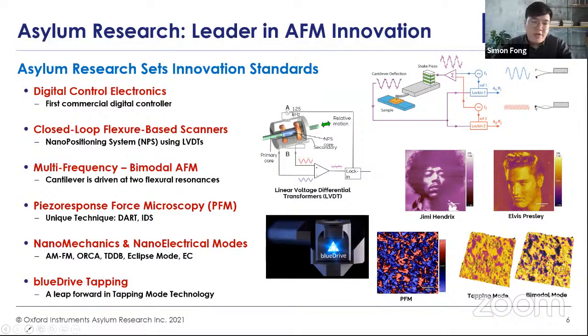We are one of the pioneers to develop closed-loop scanners for AFM using our patented LVDT sensors, which is short for linear voltage differential transformer. One of our earliest innovations is also the multi-frequency technique called the bimodal mode. It's basically a mode in which we drive the cantilever at 2 resonance frequencies.